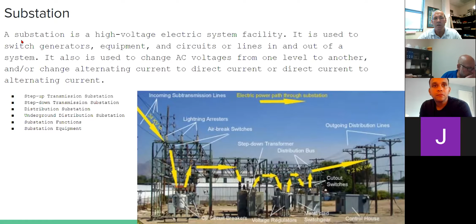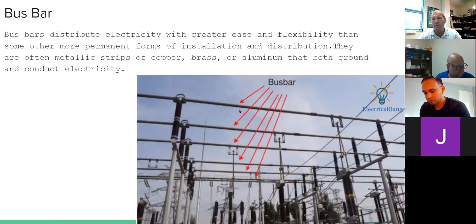Inside a substation, bus bars - these bars right here - distribute electricity with greater ease and flexibility than some other more permanent forms of installation and distribution. They are often metallic strips of copper, brass, or aluminum that both ground and conduct electricity. So I can ground these if I need to, but inside a substation, because the amps are so high, I need a better conductor, so they use bus bars in a substation.